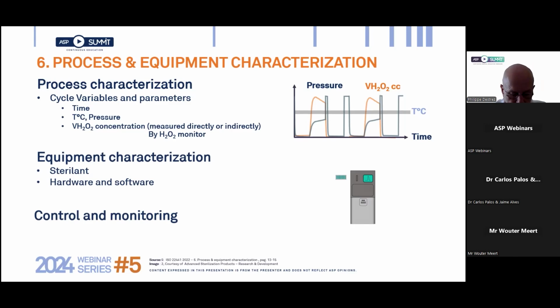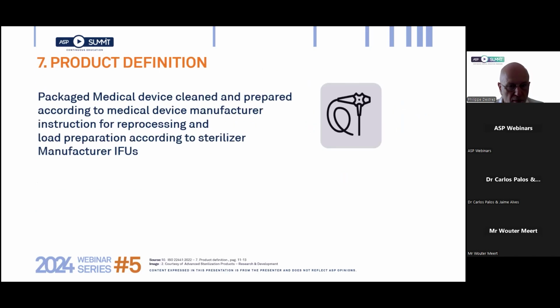Paragraph 6 also defines requirements for sterilant and equipment characterizations and for control and monitoring function. It reminds in particular that any failure of a control sensor must be detectable and information must be provided to the operator. Next slide. With the product definition, we are for the first time in the domain of responsibility of the healthcare facility. Healthcare facility will follow instructions for reprocessing that must be defined and evaluated by the medical device manufacturer. So instructions for reprocessing describe the cleaning process and specify the H2O2 cycles to be used. We'll come back to that key point in the next slide.